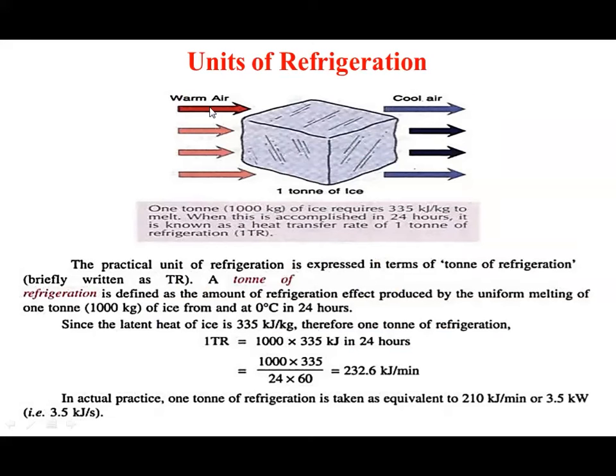So the unit of refrigeration — to measure every effect we need to express it in terms of units. The general unit used to measure refrigeration effect or cooling effect is the ton of refrigeration. A ton of refrigeration is defined as the amount of refrigeration effect produced by the melting of one ton of ice at zero degrees centigrade in 24 hours.